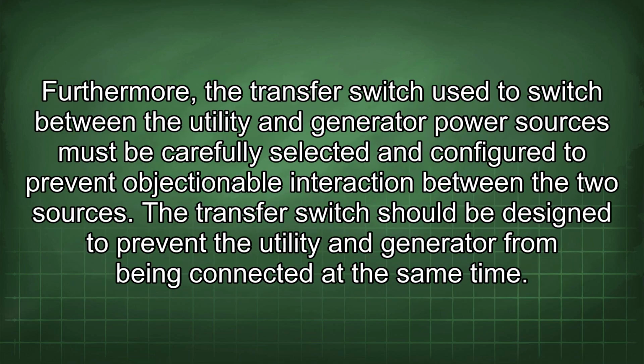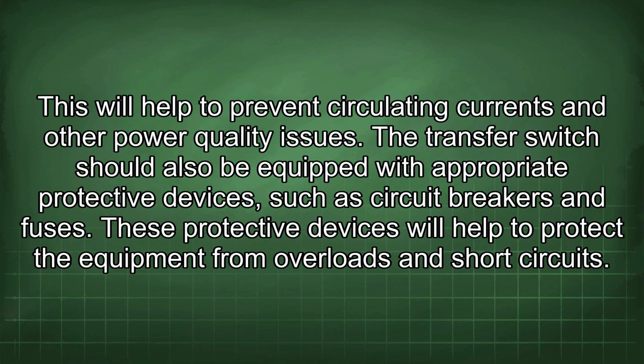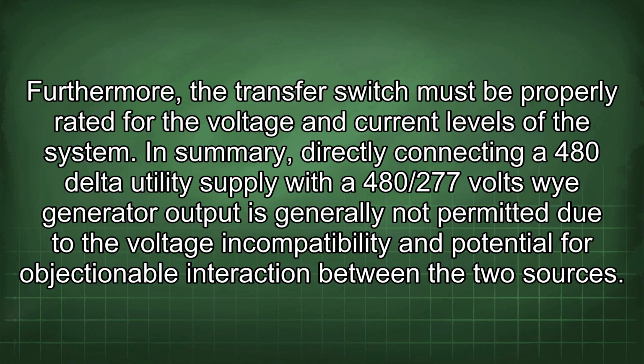Furthermore, the transfer switch used to switch between the utility and generator power sources must be carefully selected and configured to prevent objectionable interaction between the two sources. The transfer switch should be designed to prevent the utility and generator from being connected at the same time. This will help to prevent circulating currents and other power quality issues. The transfer switch should also be equipped with appropriate protective devices, such as circuit breakers and fuses. These protective devices will help to protect the equipment from overloads and short circuits. Furthermore, the transfer switch must be properly rated for the voltage and current levels of the system.